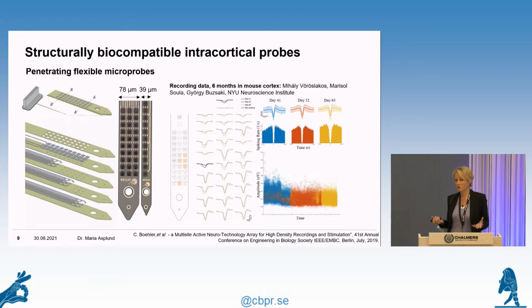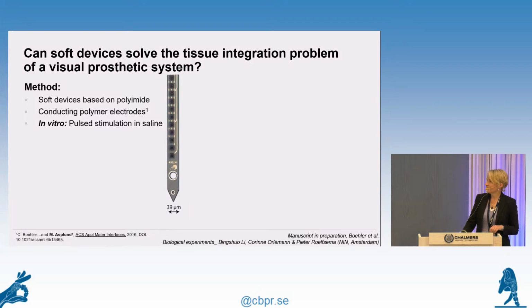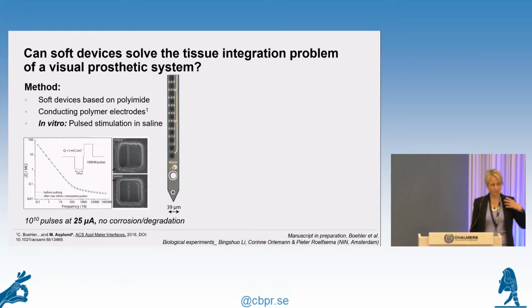So we have up to 6 months of recordings with these devices. We know they survive. So now the question is, of course, can we also use them to solve the tissue integration problems with a visual prosthetic system? So we have, first of all, of course, tested these devices a lot in simple saline, pushed a lot of pulses out of the devices to make sure that we understand at which current level they would corrode. So we are now at 10 billion pulses, and we still haven't corroded the electrodes. We know they can survive for very long usage times.